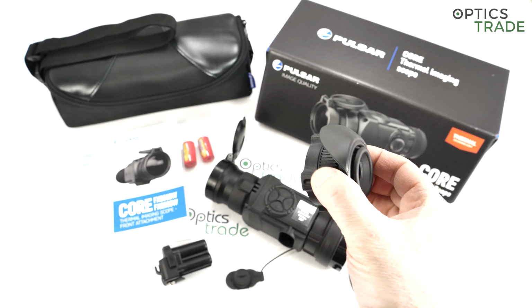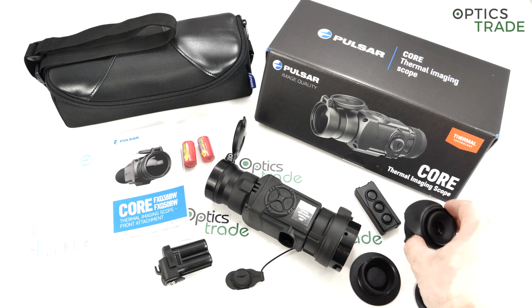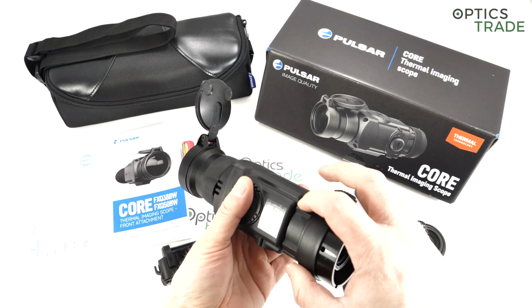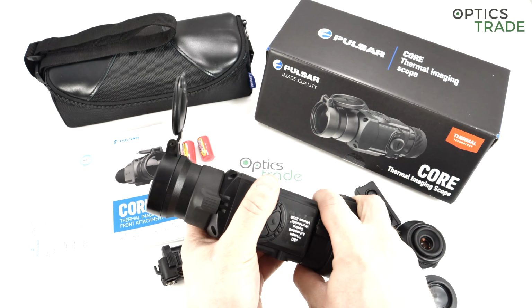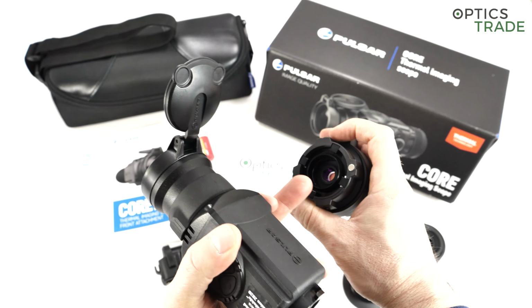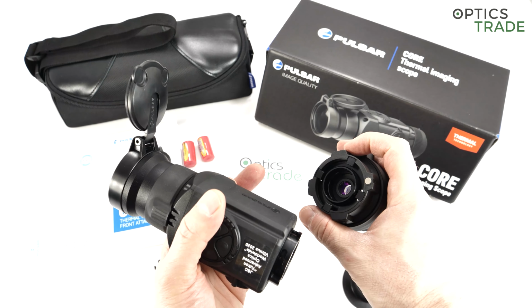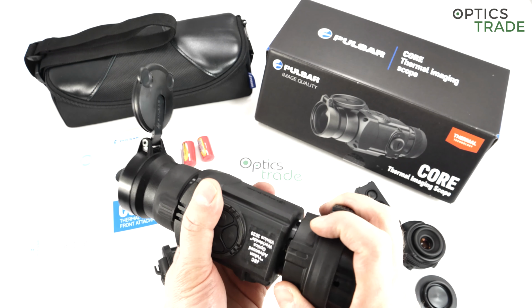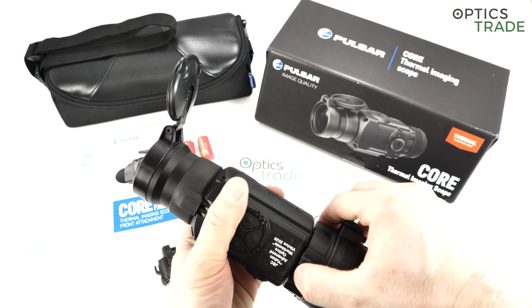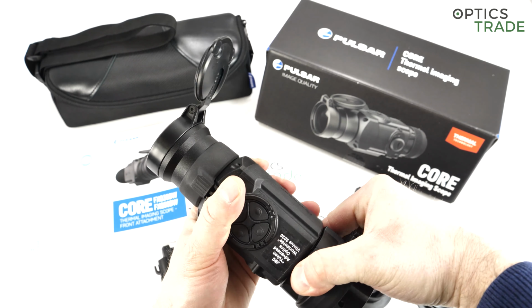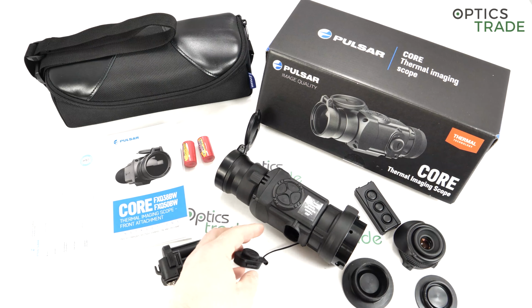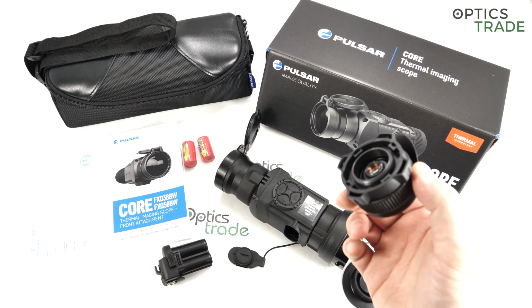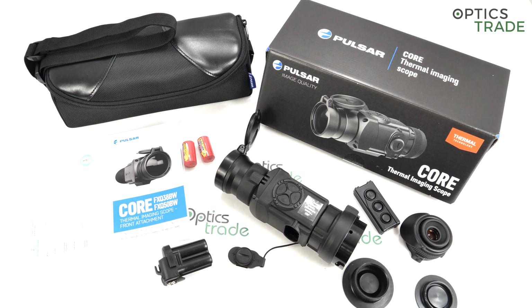The standard magnification when used as a clip-on is 1x. With this monocular it's 4x, and when the monocular is on, the device knows when this clip-on bayonet is on it and when not, with this magnet. So the device really knows how you're using it, either as a clip-on or as a monocular. When you're not having the device on your daytime optics and you're using it with this small monocular, then you're able also to use 2x digital zoom. So you get 4.1 magnification as normal and 8.2 when the digital zoom is applied.